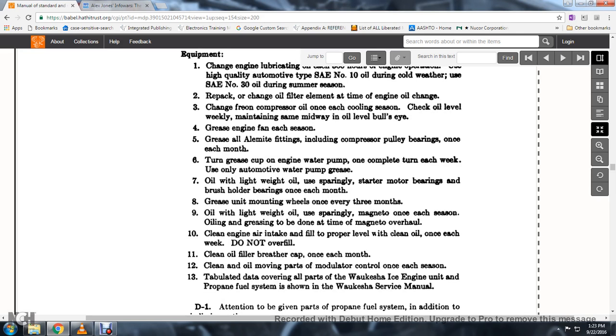Grease the engine fan each season. Grease all fittings including the compressor pulley bearings once each month. Turn the grease cup on the engine water pump one complete turn each week; use automotive water pump grease. Oil the starter motor bearings and brush holder bearings once each month. Grease the unit mounting wheels once every three months. Oil the magneto once each season using light-weight oil sparingly; oiling and greasing to be done at the time of the magneto overhaul.